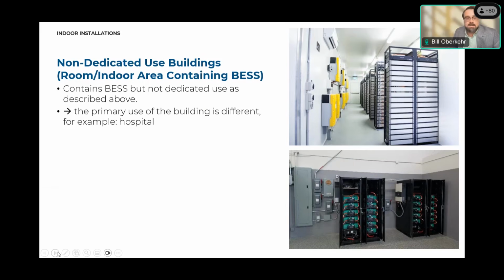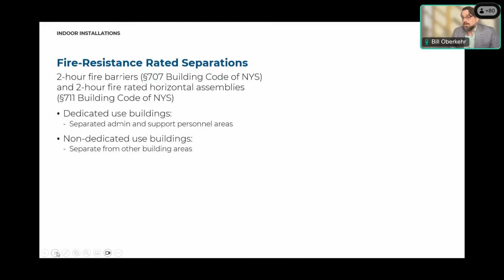Next slide, please. Two-hour fire barriers, once again, we did cover this. This is part of the general requirements too. 2 hour fire barriers per section 707 of the building code. And that includes, again, the sealing of the room or area containing the battery. Next slide, please.